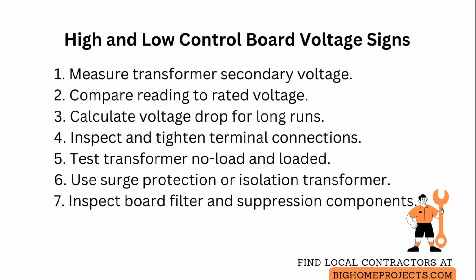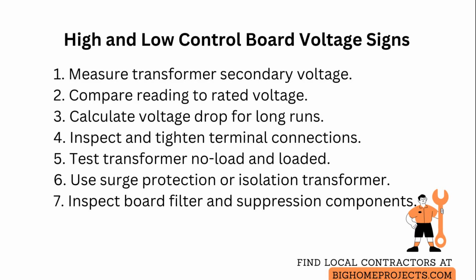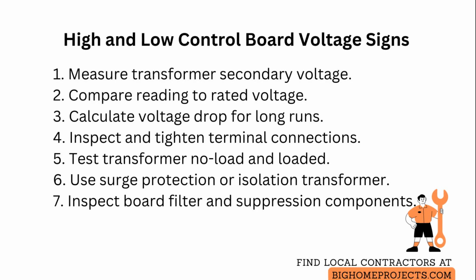Test the transformer under both no-load and loaded conditions. No-load readings can be slightly higher than rated due to regulation, but if loaded voltage collapses significantly, suspect internal winding damage or external overload and prepare to replace the transformer.